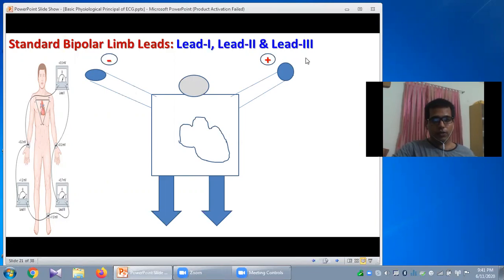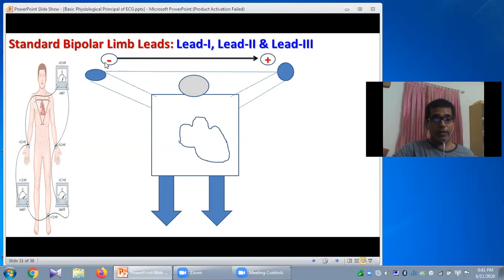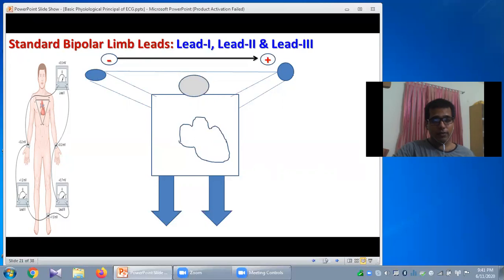Here is the left arm attached to a positive electrode and this is the right arm where the negative electrode is placed, connected to a galvanometer forming the circuit of Lead 1. The direction of Lead 1 is from right arm to the left arm — negative terminal to positive terminal. The positive terminal is also considered the exploring electrode or camera eye. A parallel line drawn along the Lead 1 axis passing across the center of the heart indicates the axis of Lead 1.